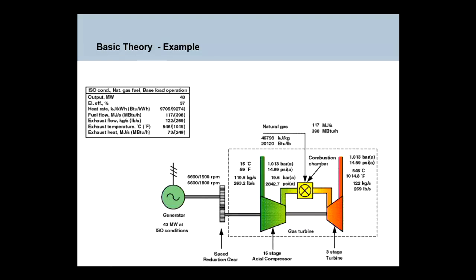Okay. There's a slide here for your notes, which I call a basic theory slide. So in this particular gas turbine, we're drawing air in. This is a 43 megawatt machine. We're drawing air into the compressor. It's compressed, heated up slightly. Natural gas is brought into the combustion chamber. You produce then hot exhaust gas, which expands through a three-stage turbine and out to atmosphere. In this case, we're driving a generator through a gearbox. So in some cases, for smaller gas turbines, you can get better efficiency if this machine is spinning at higher speeds than that set by the generator. So then you have a gearbox in between the turbine and the generator.